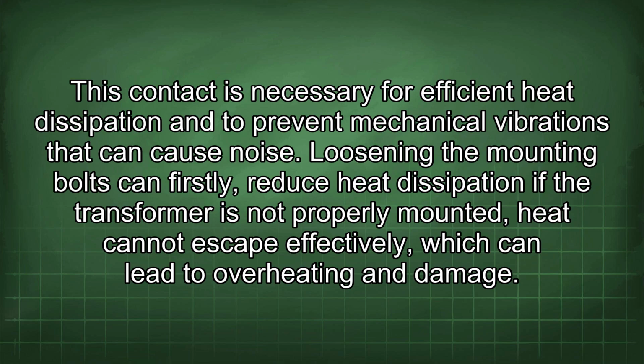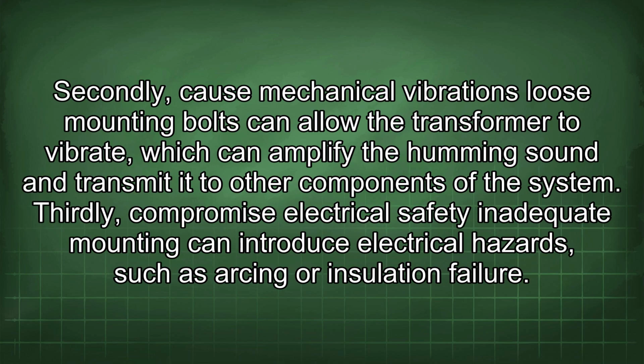Loosening the mounting bolts can, firstly, reduce heat dissipation. If the transformer is not properly mounted, heat cannot escape effectively, which can lead to overheating and damage. Secondly, it can cause mechanical vibrations. Loose mounting bolts can allow the transformer to vibrate, which can amplify the humming sound and transmit it to other components of the system. Thirdly, it can compromise electrical safety. Inadequate mounting can introduce electrical hazards, such as arcing or insulation failure.